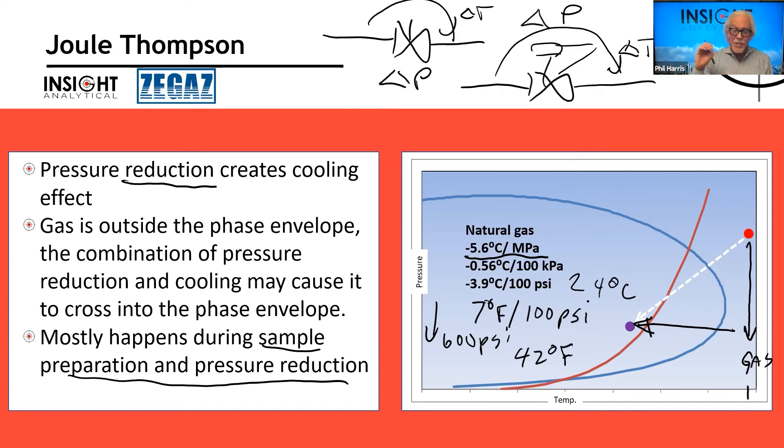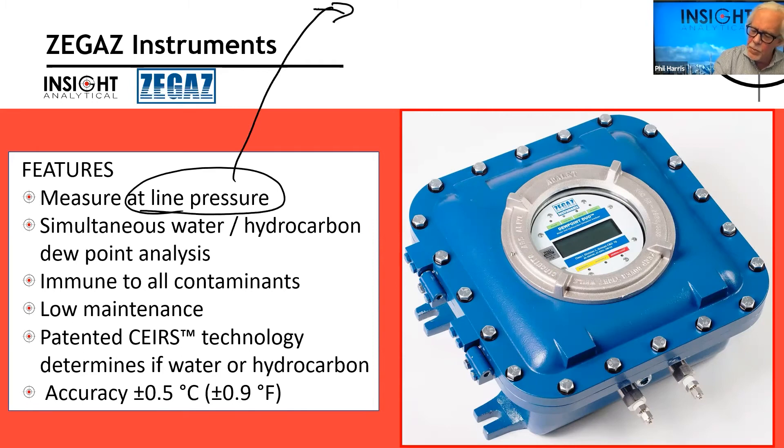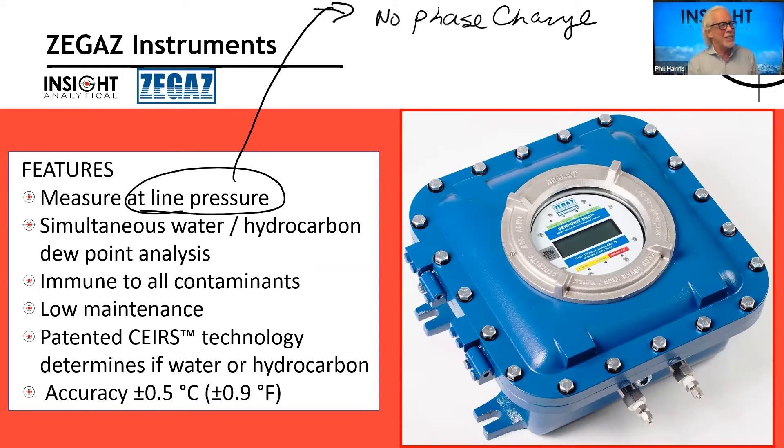Because hitting dewpoints can cause so many issues, that's why we'd like to be able to measure it. One of the ways is with an analyzer manufactured by ZEGAZ Instruments, which has some unique features. It measures everything at line pressure — this is important because one of the first things we noted is that when we drop the pressure, we can cause ourselves issues. So measuring at line pressure makes us less likely to have phase change.